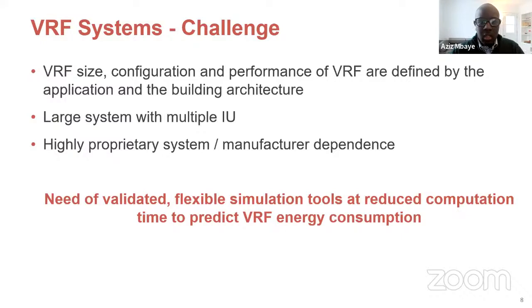And moreover, as HVAC professionals, you guys might know, the VRF designs, the piping sizing, and even the control system are performed using some proprietary software, usually provided by the manufacturer. This means that unlike a more traditional non-VRF heat pump system, like just a chilled water system, a building owner is tied to the manufacturer for the entire life of the system. And it is important also to note that one cannot integrate a VRF system component from one manufacturer into a system provided by another manufacturer.